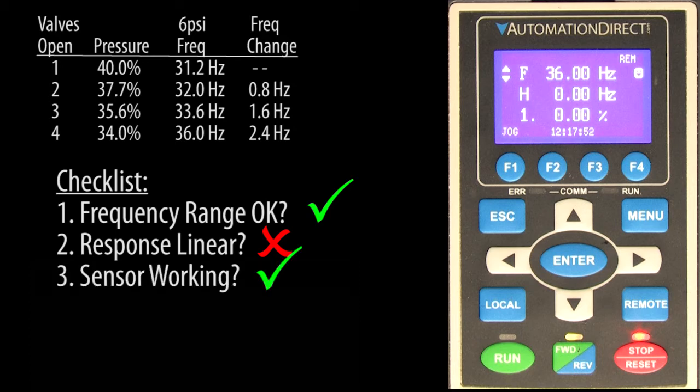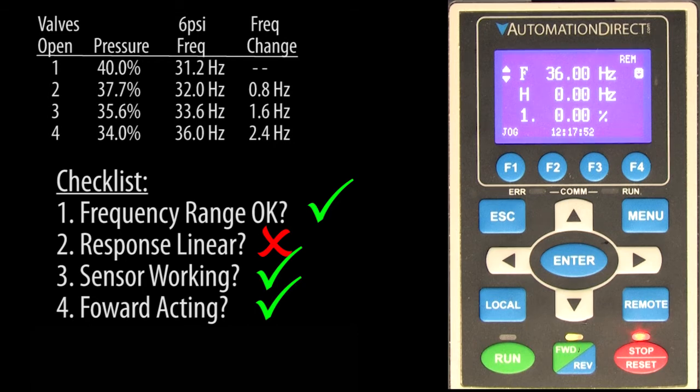We know our sensor is working and that when the motor speeds up, the sensor value goes up. We call that a forward acting system. A reverse acting system would be something like a cooling system where increasing the motor speed reduces the temperature sensor's output.